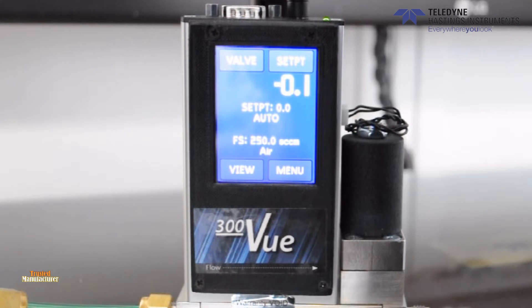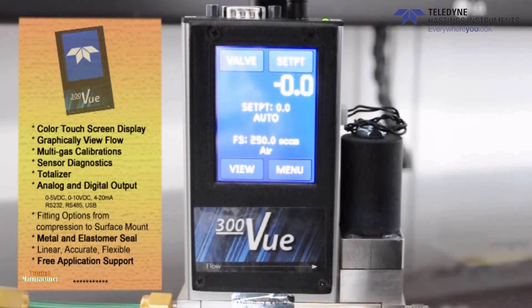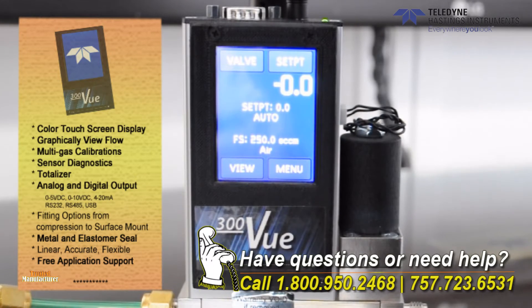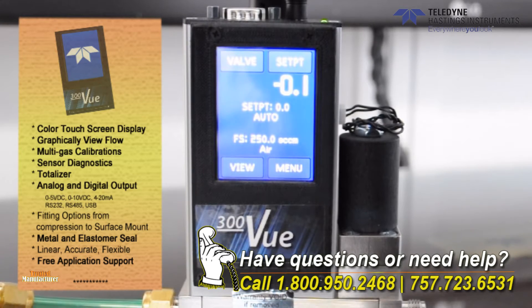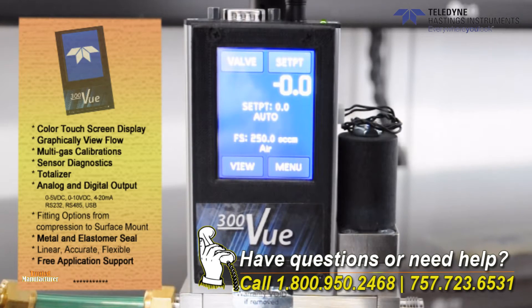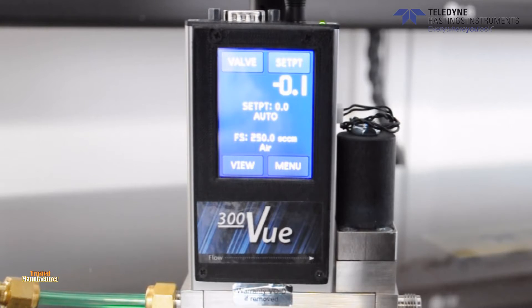The 300Vue has a 9-pin D connector and a 3.5mm TRRS jack for analog and digital communications respectively. The 300Vue is available with many different analog input and output options such as 0-5V, 0-10V, 0-20mA, and 4-20mA. All digital instruments have the ability to communicate via RS-232 and RS-485. We will talk about this later in the video.